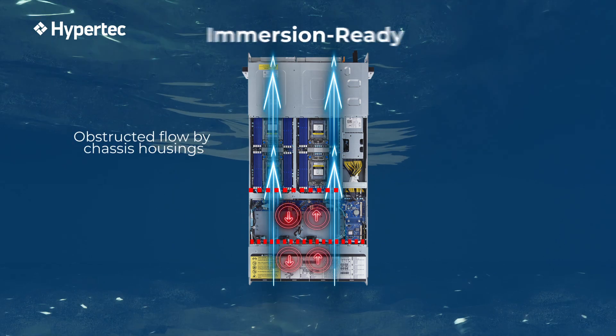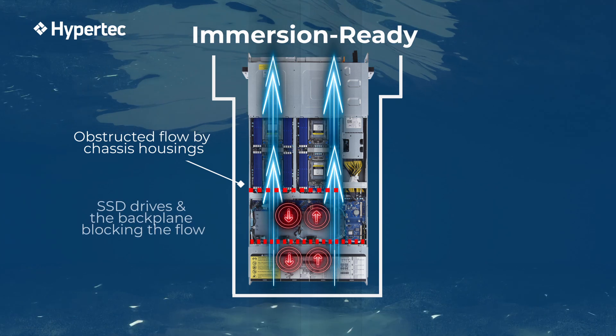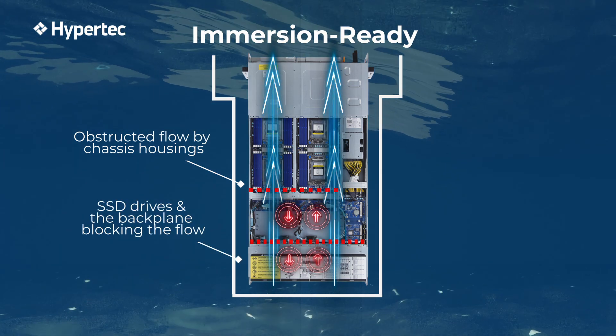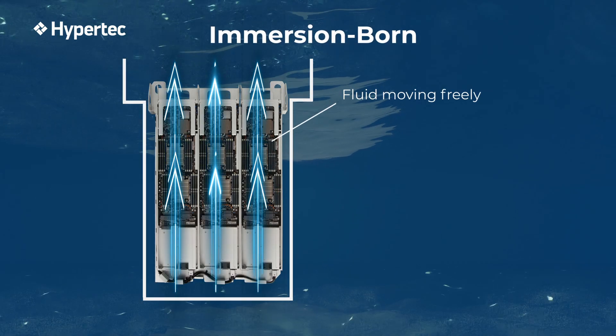In Retrofitted Immersion Ready hardware, the liquid flow encounters obstacles navigating through chassis housings and a backplane. Additionally, the absence of side openings, originally intended for air, further impedes the free flow. Hypertec specifically engineered a chassis to help the flow of the liquid from bottom to top.